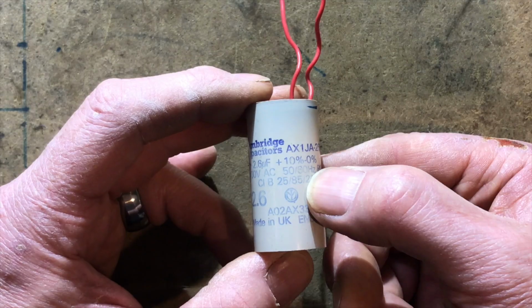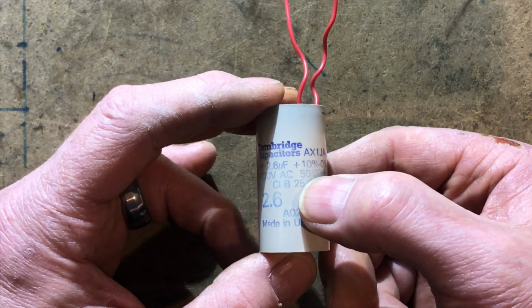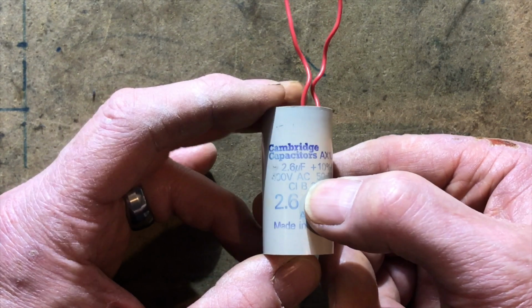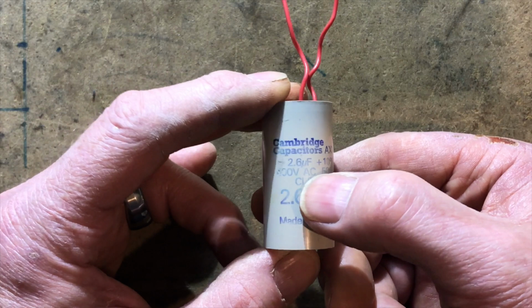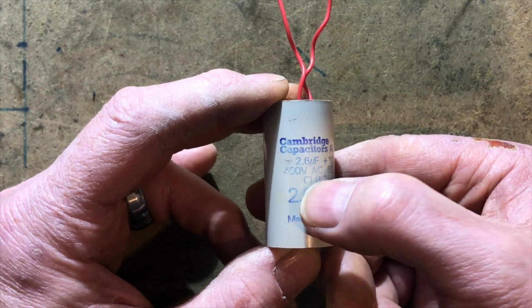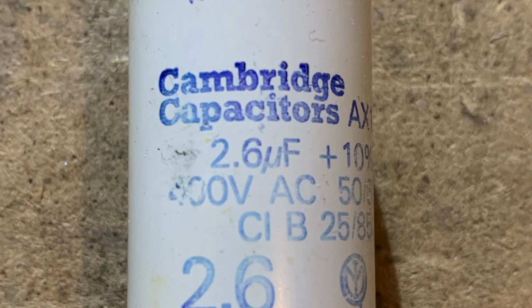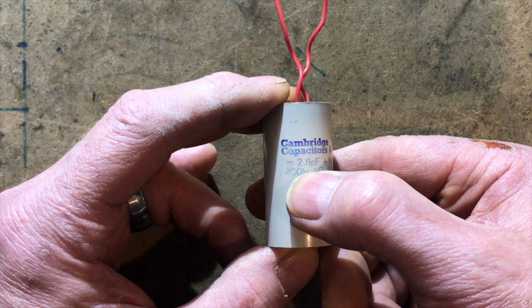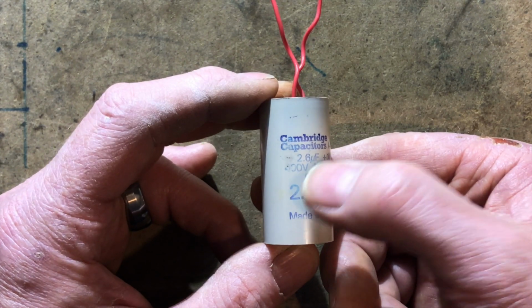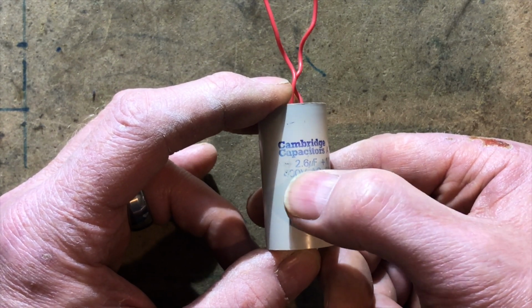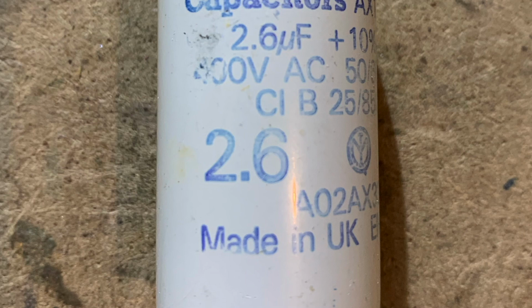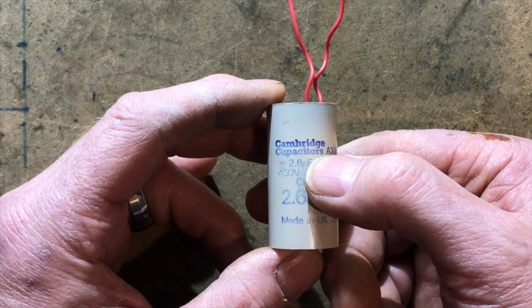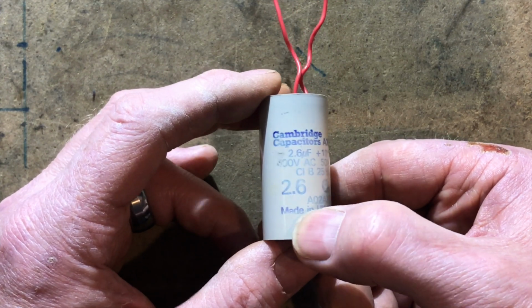So in the UK we're 50 hertz, in America they're 60 hertz. Okay, so that's where this 50-60 comes from, and that's your 50 cycles per second, I think. Not being an electrician, but I think that's what that means. Now the 400 volts AC is what it can take. So if this only said 100 volts AC and you put it in the pump, because the pump is 230 volts, this would explode. Okay, so that's what that means. That's the voltage it can take, 400 volts. And then the big 2.6 is just the microfarad. So that's what it means on this start capacitor, and that's the start capacitor on this Grundfos pump.